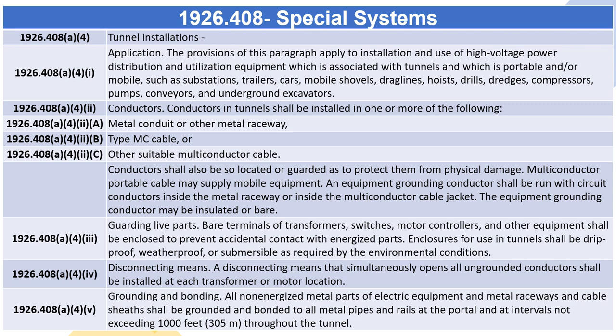1926.408(A)(4)(ii) — Conductors. Conductors in tunnels shall be installed in one or more of the following: (A) metal conduit or other metal raceway; (B) Type M-C cable; (C) other suitable multiconductor cable. Conductors shall also be so located or guarded as to protect them from physical damage. Multi-conductor portable cable may supply mobile equipment. An equipment grounding conductor shall be run with circuit conductors inside the metal raceway or inside the multi-conductor cable jacket. The equipment grounding conductor may be insulated or bare.